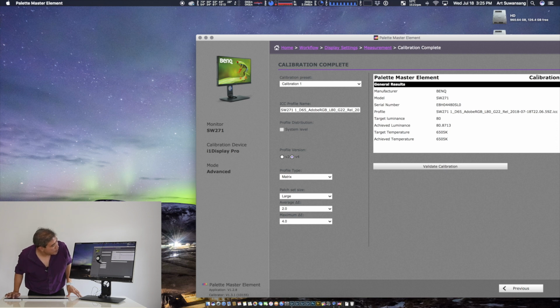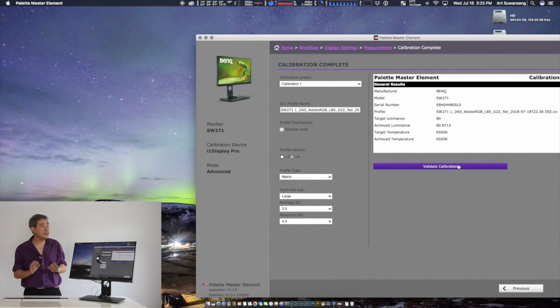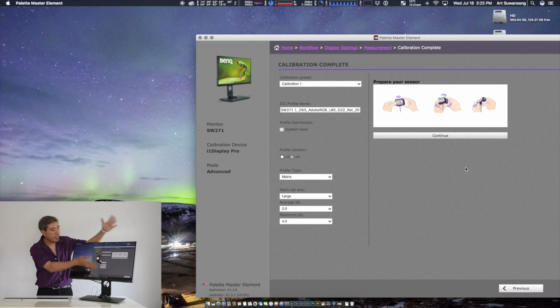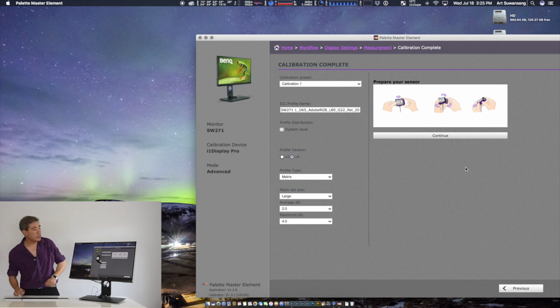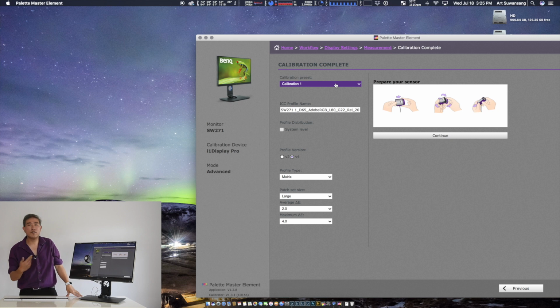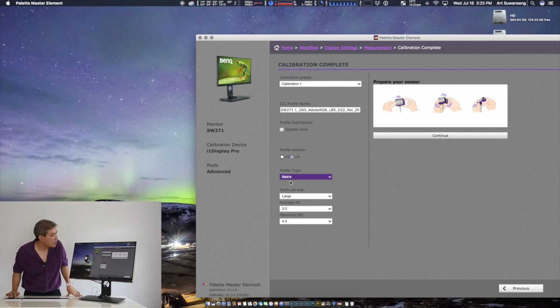Now before I finish here, what I want to do is come into validate calibration. Validate calibration will do a couple things. It'll tell me to flip the colorimeter again, which in this case I have. It will ask you a few questions, such as what calibration you want to validate. In this case we just calibrated calibration slot 1, so we're going to do that. What profile version, what profile type, matrix, and so forth.